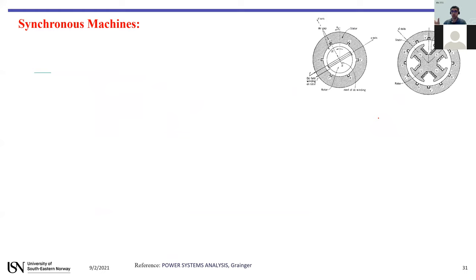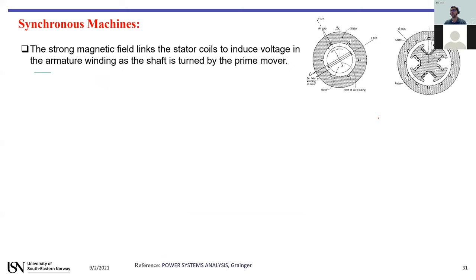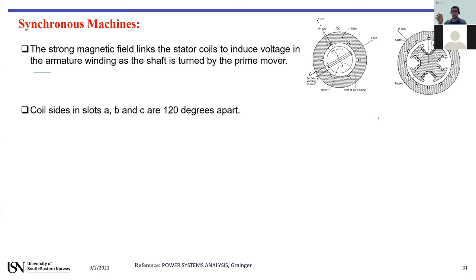For both rotor types, the strong magnetic field links the stator coil to induce voltage in the armature. The rotor is mounted on the shaft driven by the prime mover. Since we have three phases, the coil sides are placed in three slots that are 120 degrees apart — coil a and a', b and b', and c and c' — similarly for the salient pole rotor.